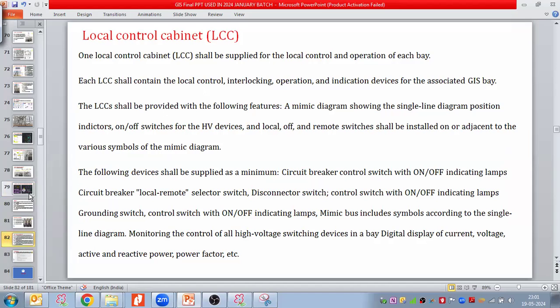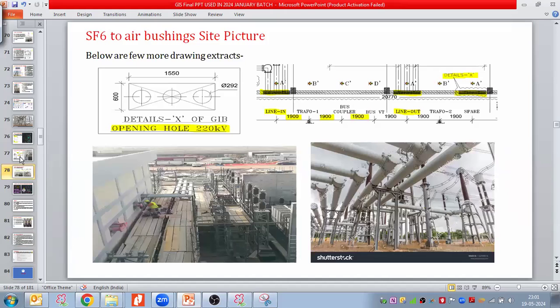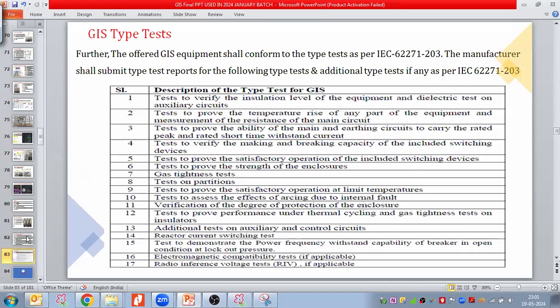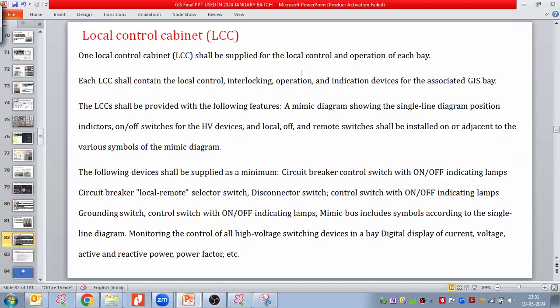So in the GIS, for each bay, we take a local control cabinet. One local control cabinet shall be supplied for the local control and operation of each bay. Each local control cabinet shall contain the local control, interlocking, operation, and indication devices for the associated GIS bay. And there should be a mimic diagram as well. The LCC shall be provided with the following features: a mimic diagram showing the single line diagram positions, indicators, and on-off switches for the devices, and local-off and remote switching shall be installed adjacent to the various symbols of the mimic diagram.